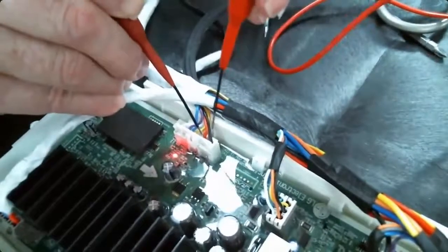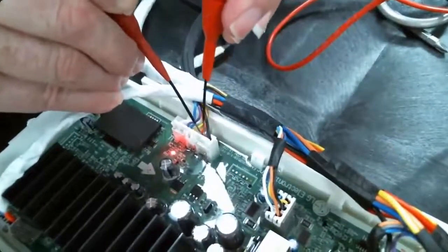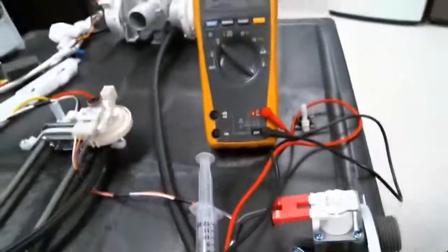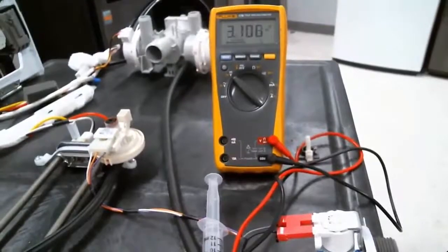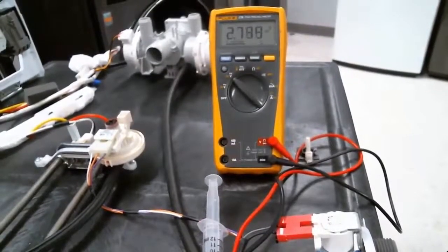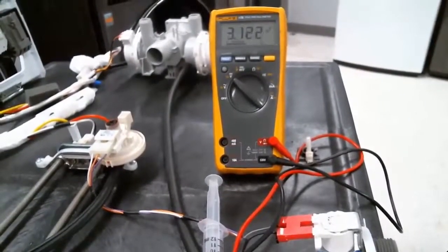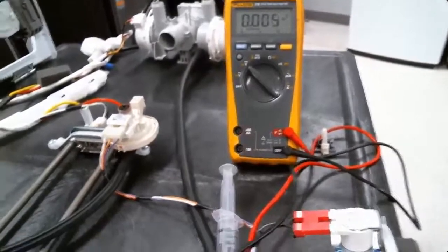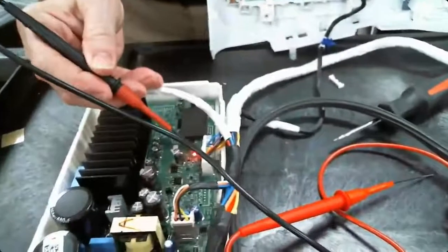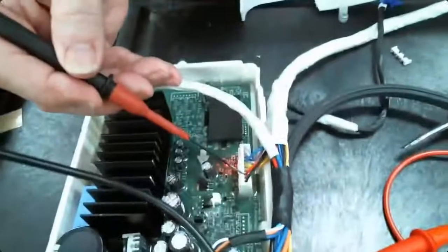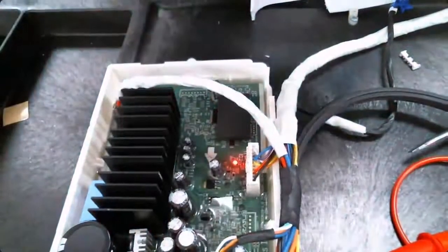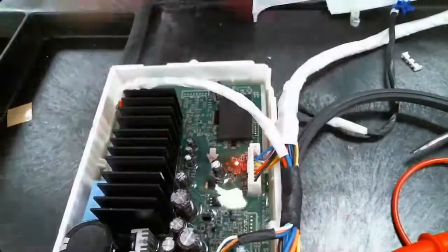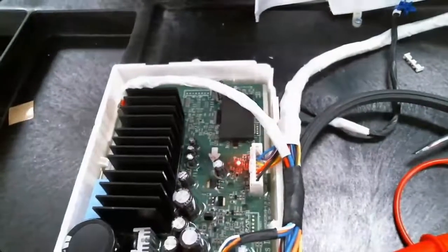Next, I'm going to go to the brown wire and get a similar reading. Let me work this in there. You can see it's a little less voltage, but still pulsating - you'll get either a 5 or a 0. Remember, on one side it's transmit, and when it gets to the other side, it's receive. The same wire that was receive becomes transmit on the other board, so they're just opposite going from one board to the other.